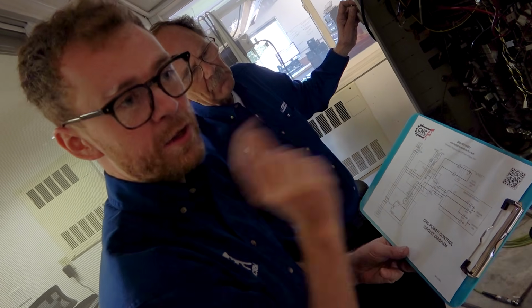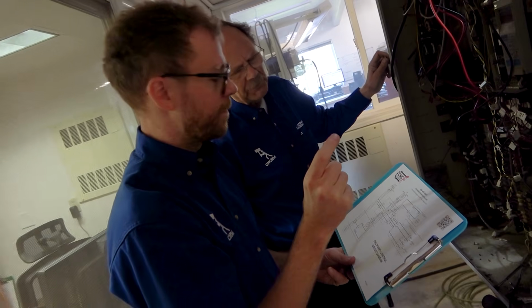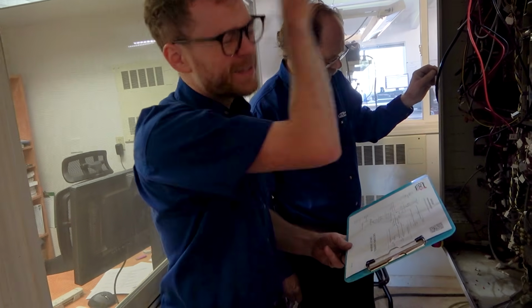This relay, when it's energized, opens. When it opens... oh, it's closed. That's why. It's normally closed, which messed up my voltage reading.